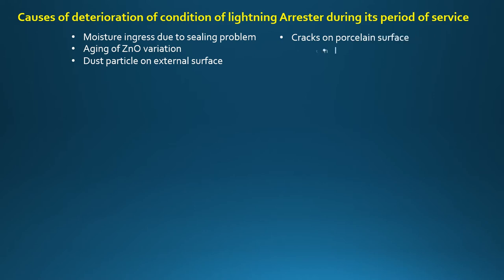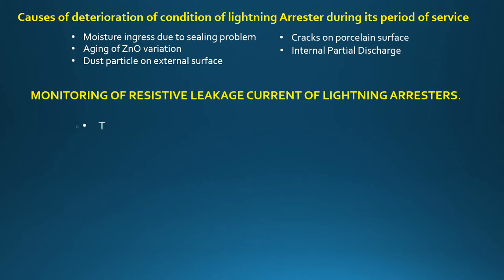Internal partial discharge is another cause of deterioration. To avoid failure of the lightning arrester, it is necessary to monitor its health, because if a lightning arrester fails it explodes with porcelain splinters, and apart from creating a short circuit, it also mechanically damages other nearby equipment.